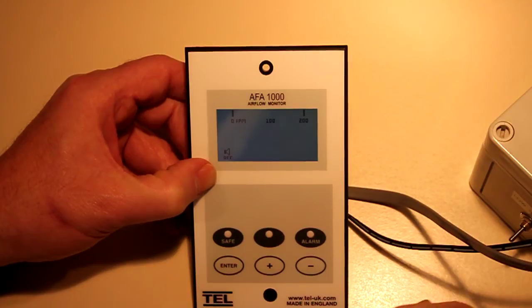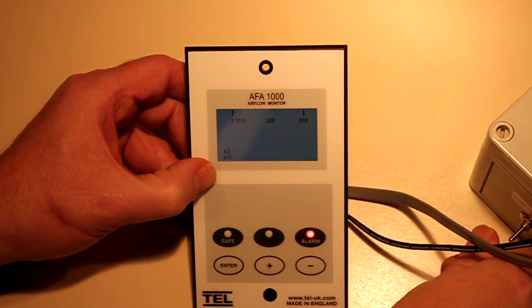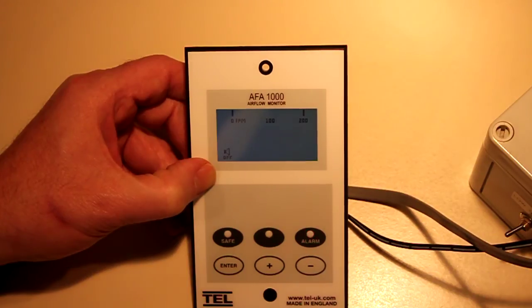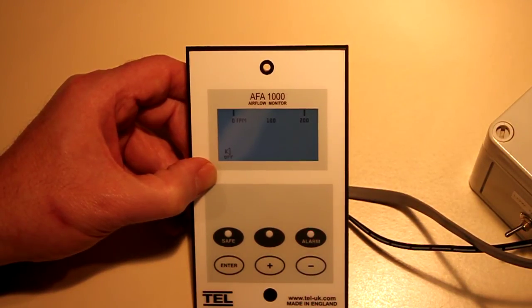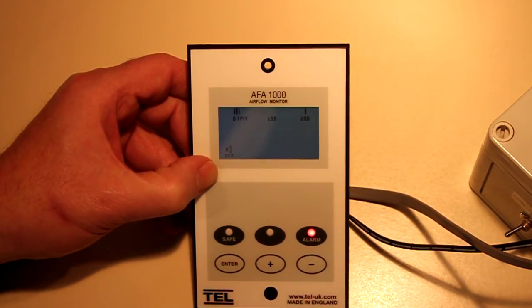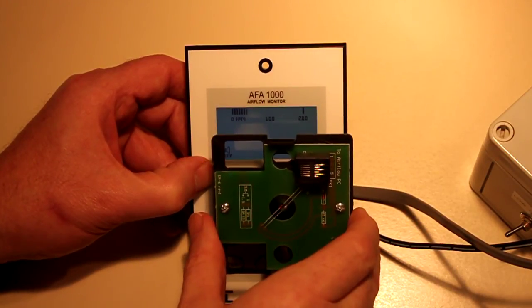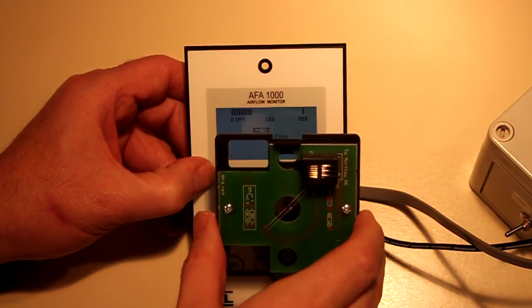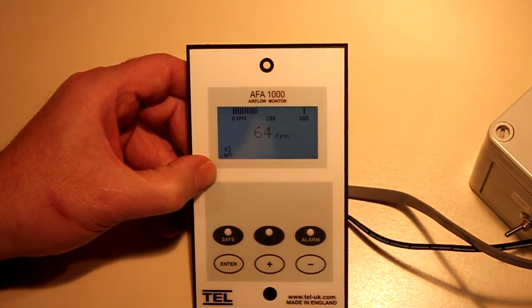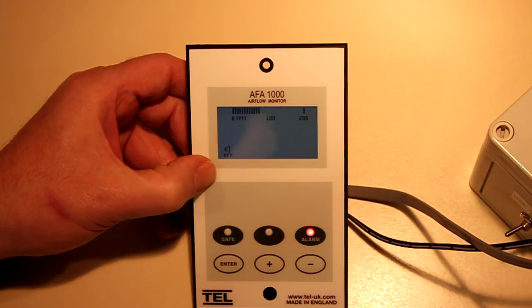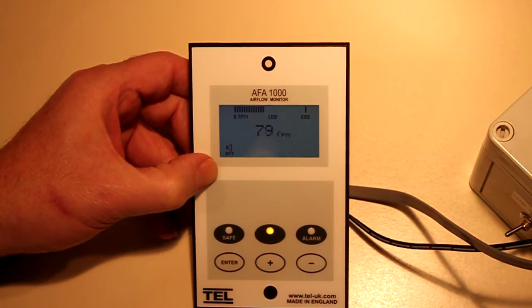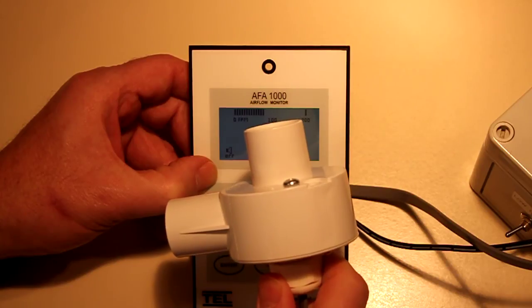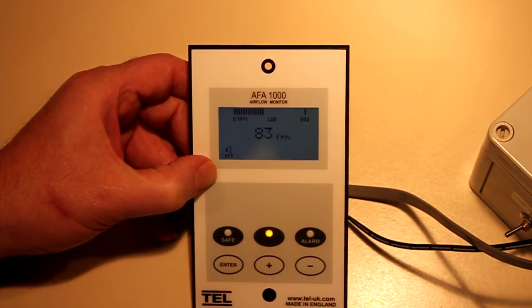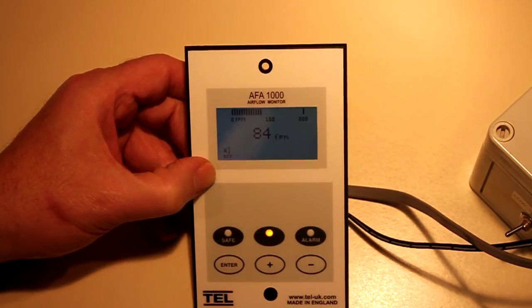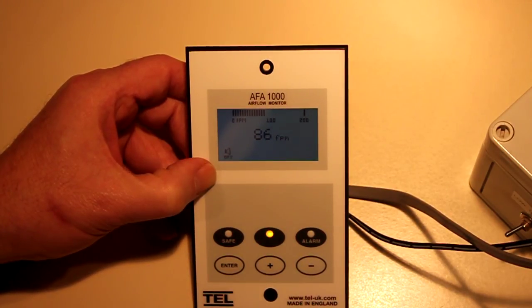The AFA 1000 also can communicate with a building management system via BACnet or Modbus by use of an accessory adapter cable that connects to the communications port. The AFA 1000's airflow sensor utilizes large, stable, and reliable sensor elements. The standard monitor comes with a post-mounted airflow sensor and airflow tube that connects to a hole on the fume hood's inner sidewall. Also available is an inline sensor using the same hot wire components that is installed between the inner and outer sidewalls, connected using the same style of air hose to a hole on the fume hood post. The AFA 1000 will be mounted on the post of the hood. All necessary parts, as well as an owner's manual, are included in a boxed kit.